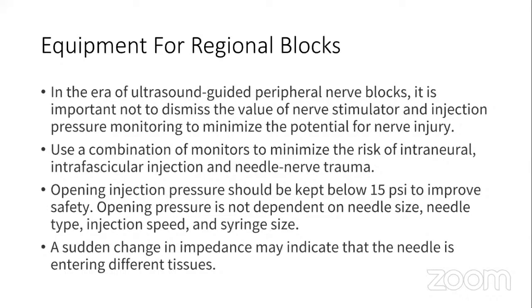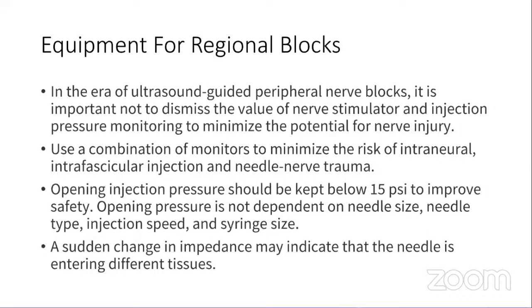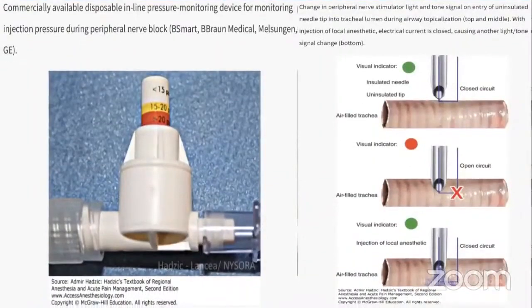You must remember that a sudden change in impedance when you are using a nerve locator may indicate that the needle is entering a tissue other than what is intended. So you have to be careful. Now there are various inline pressure monitoring devices available for nerve blocks, and they can measure the injection pressure, and that is what is important for us to monitor.